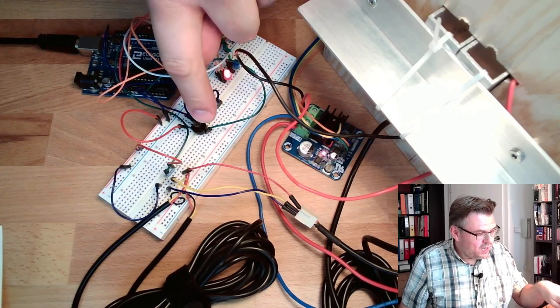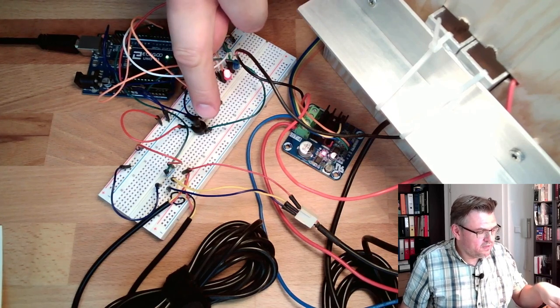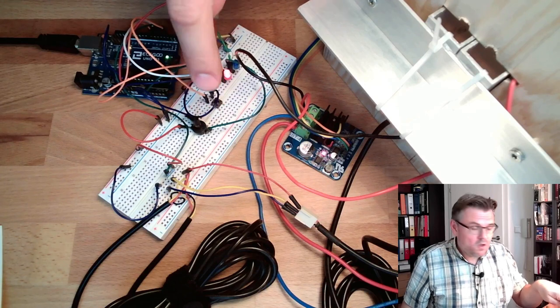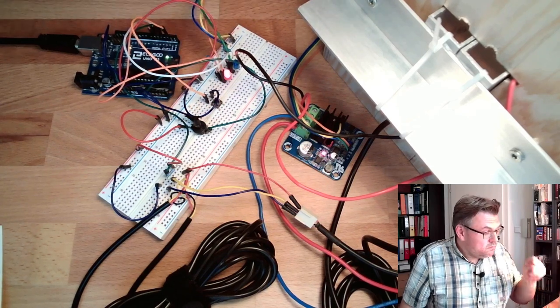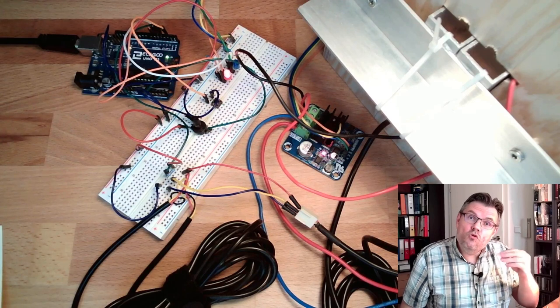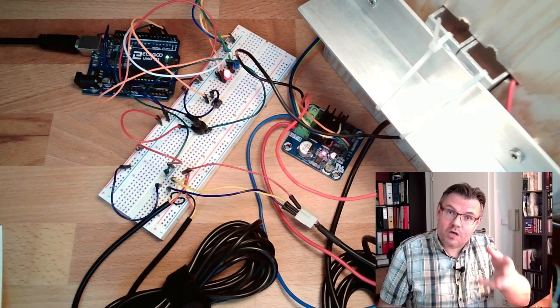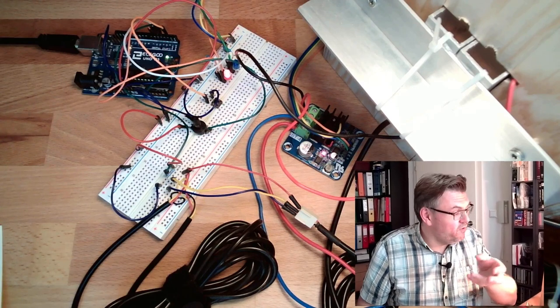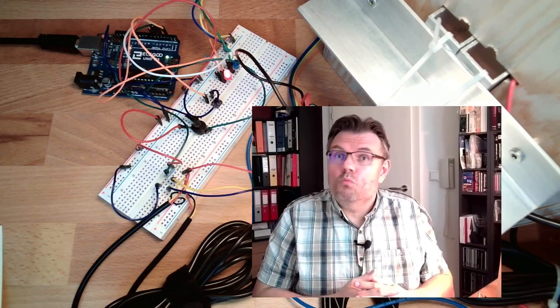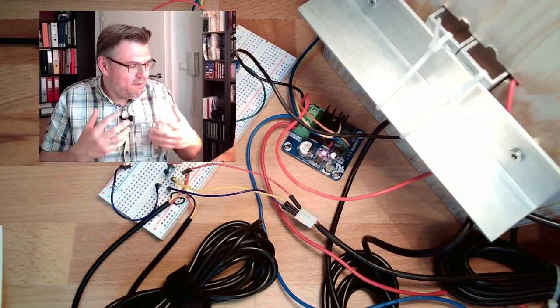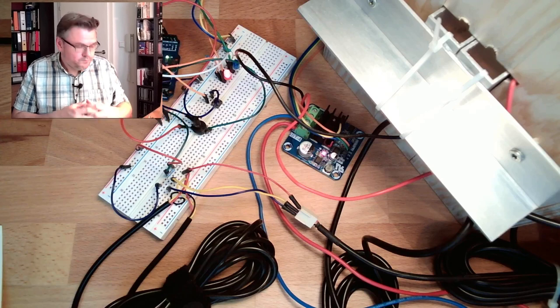I can adjust the correcting variable with the help of this potentiometer here. I will trigger a new correcting variable, do a correcting variable jump, and out of the reaction of the system we can read out what it is and if it's controllable or not. This is the goal: we want to identify the system.